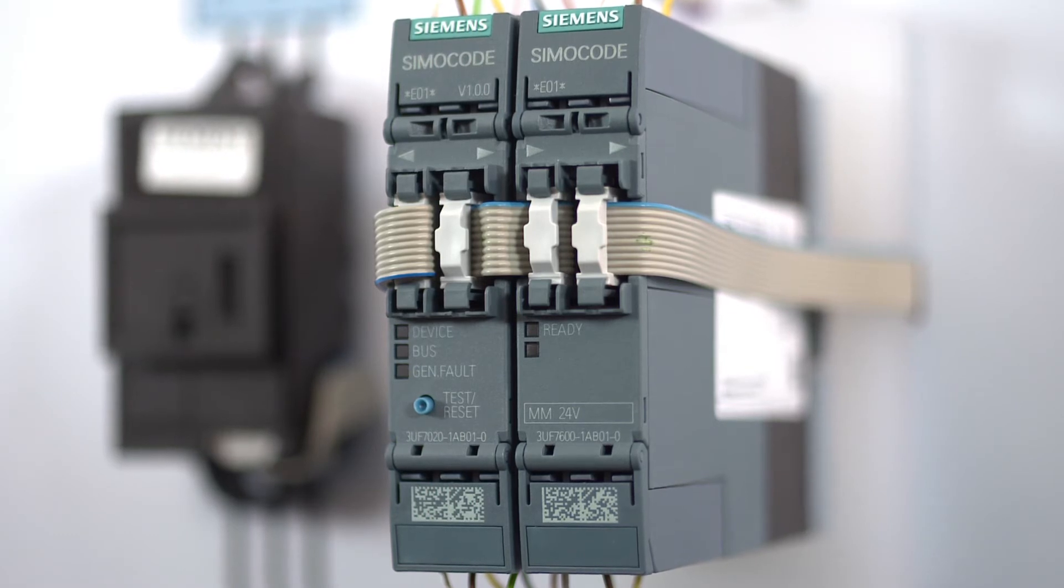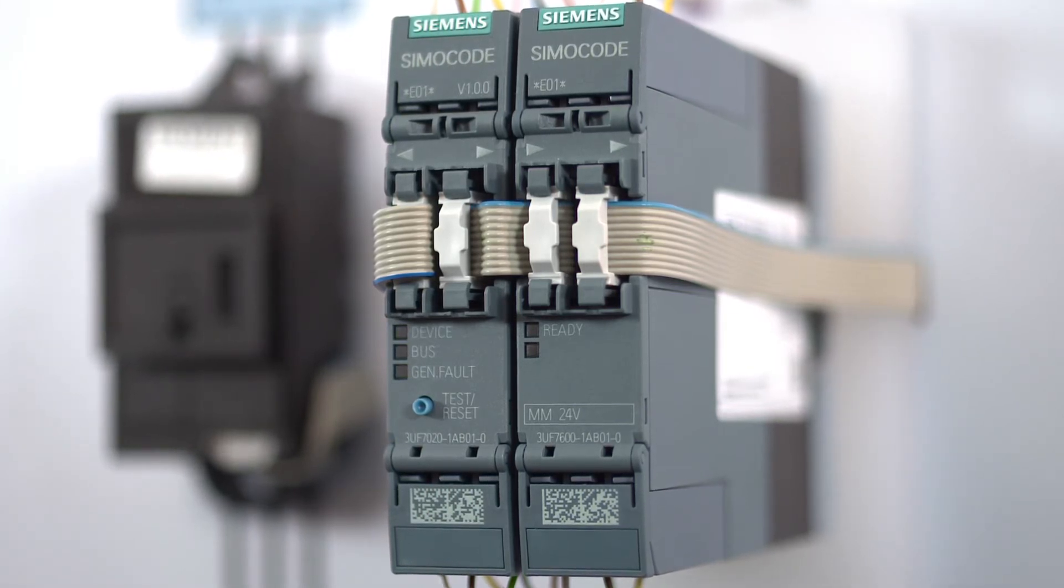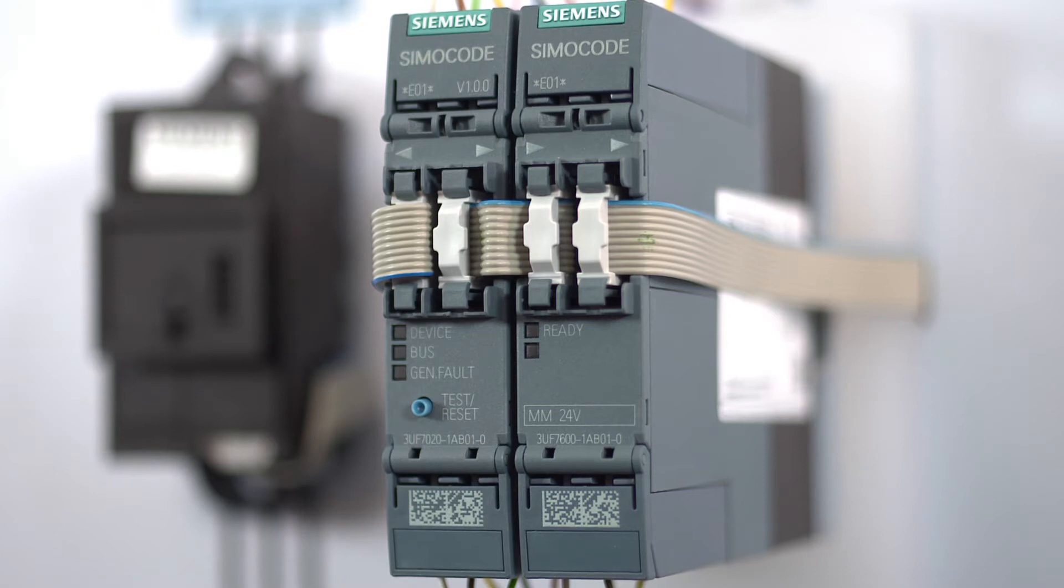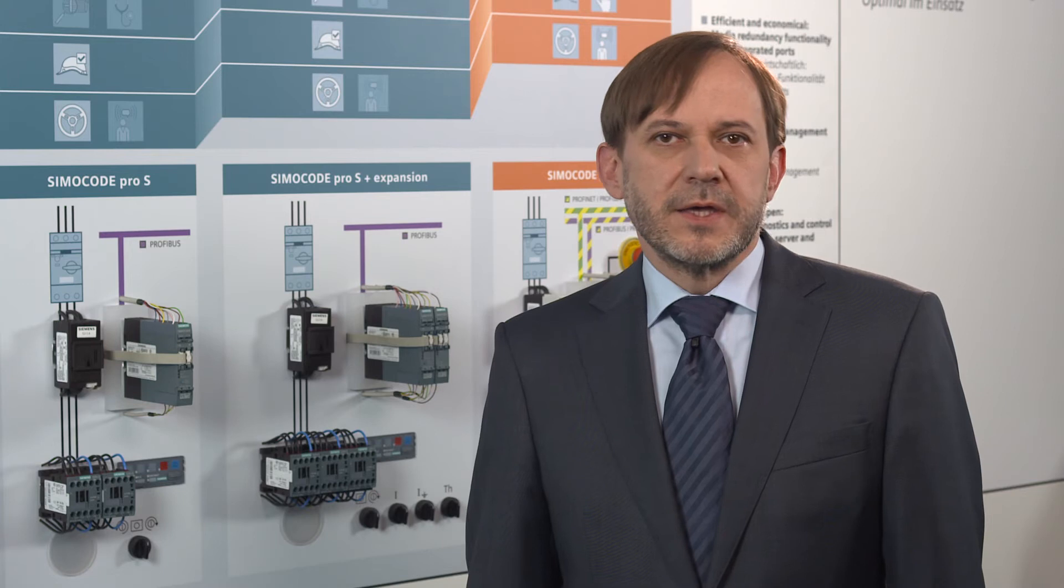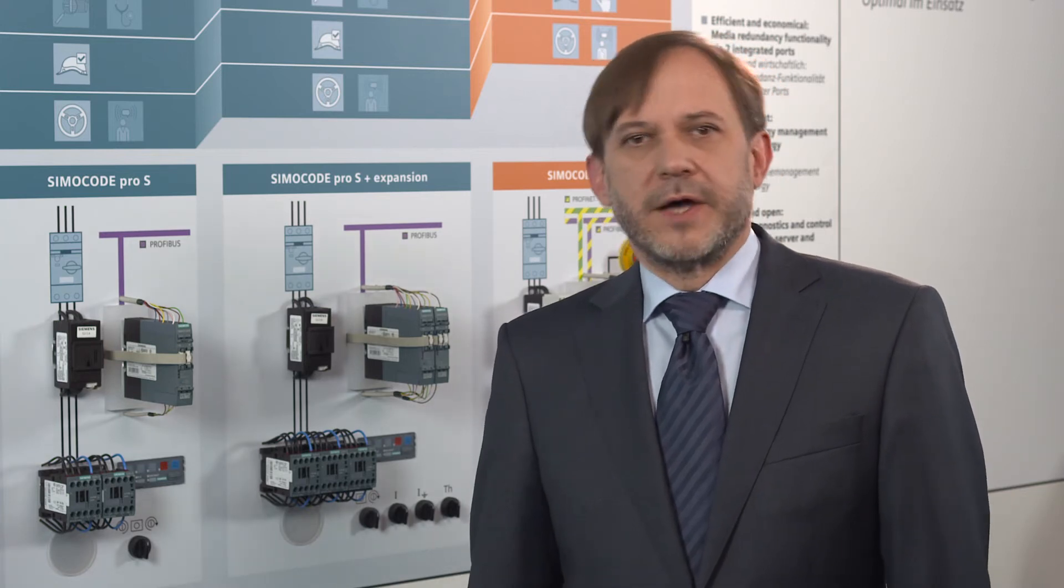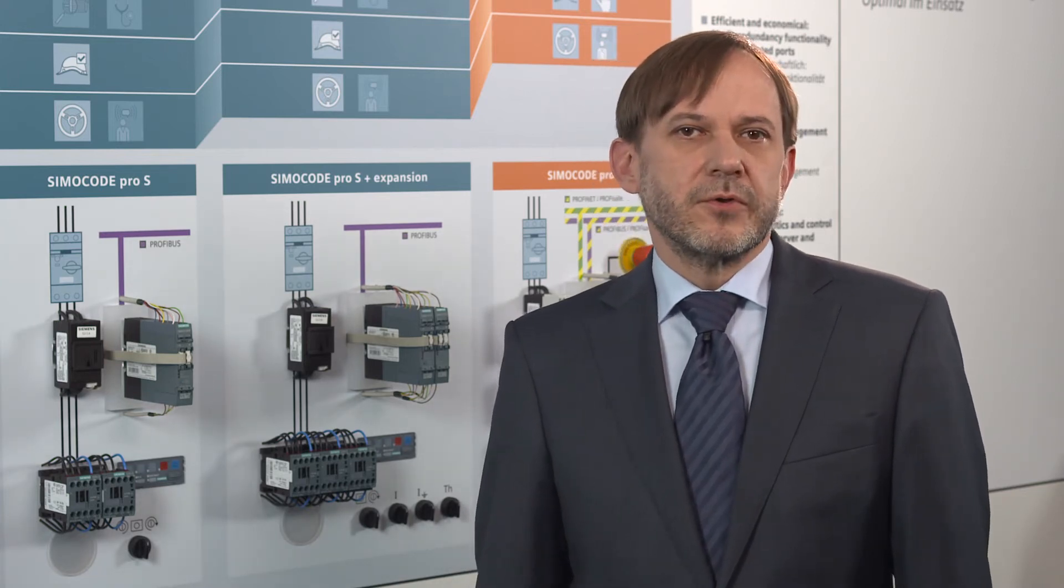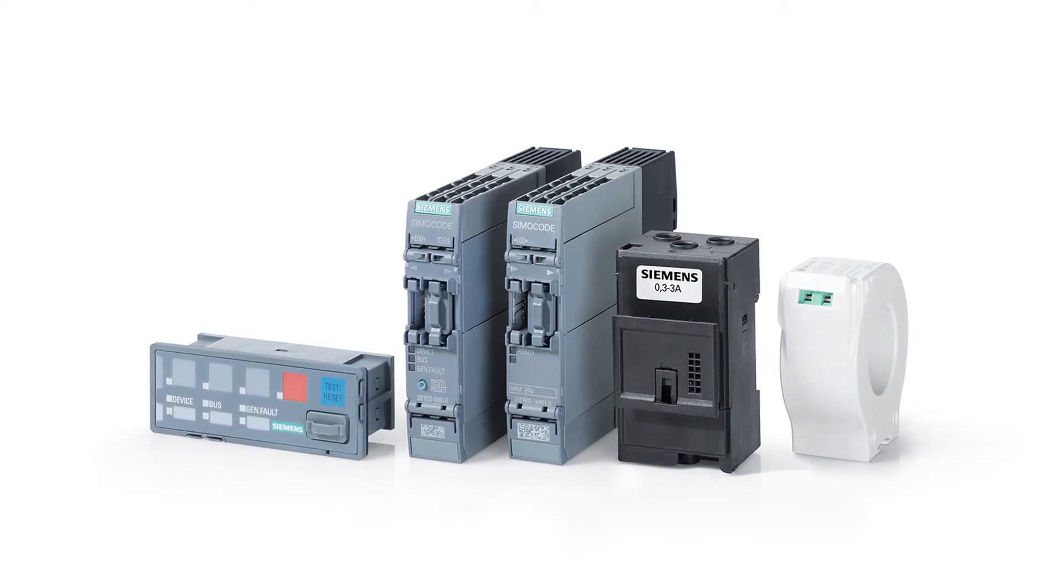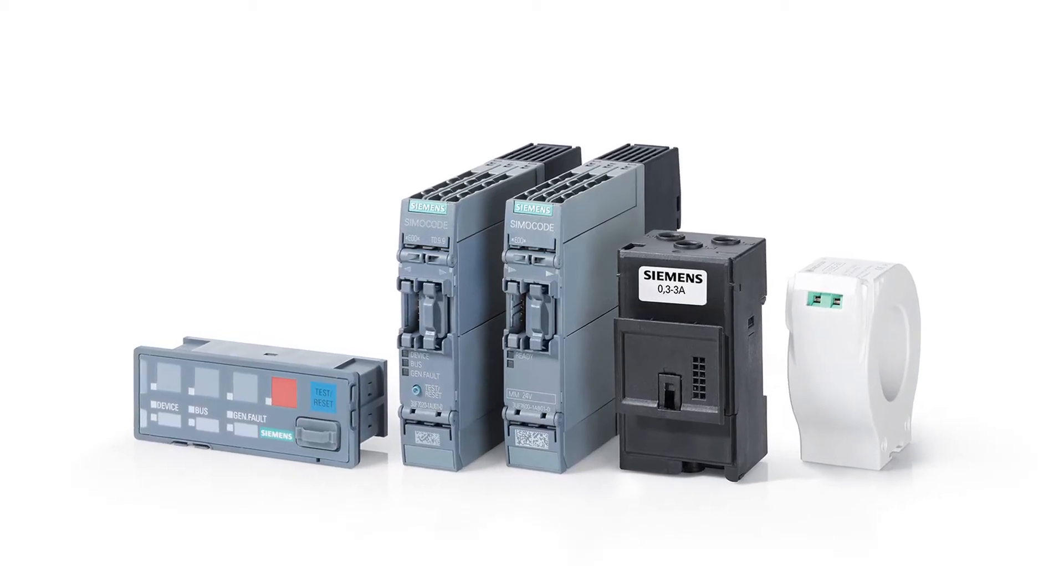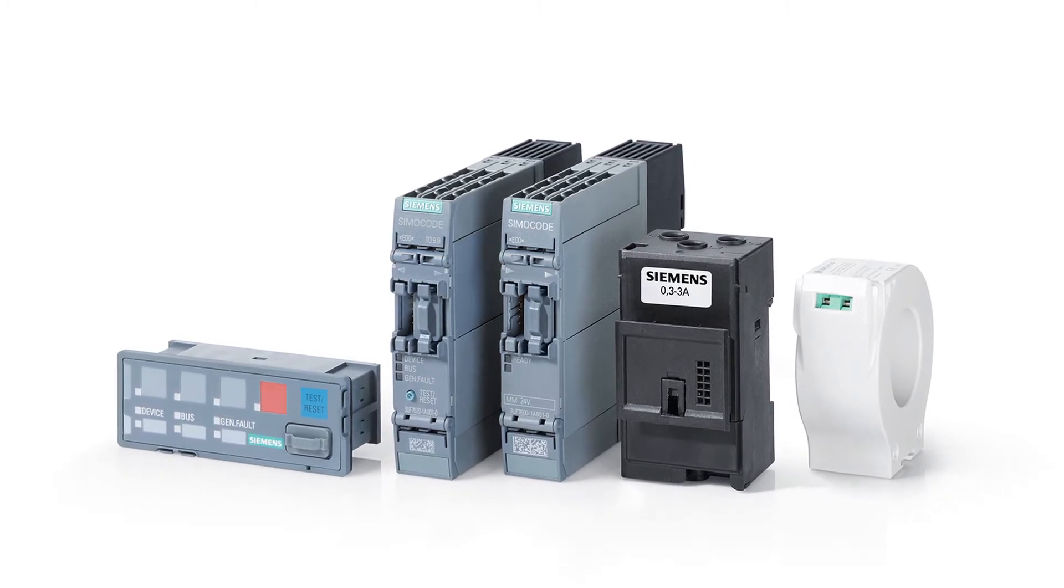The optional multifunction module expands the basic unit with four additional digital inputs with 24V or 110-240V as well as two relay outputs. Other control functions such as soft starting or star delta starting are thus possible. It is also possible to connect a residual current transformer for measuring the earth fault current and a temperature sensor.